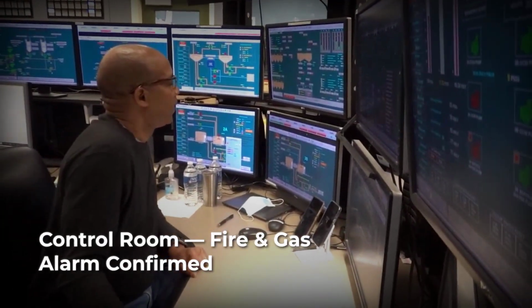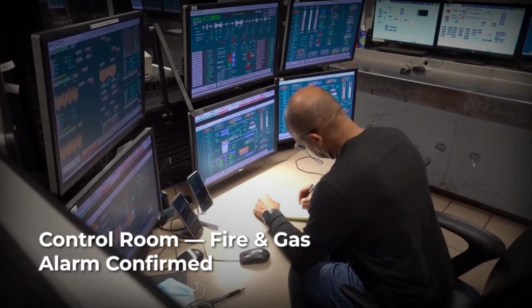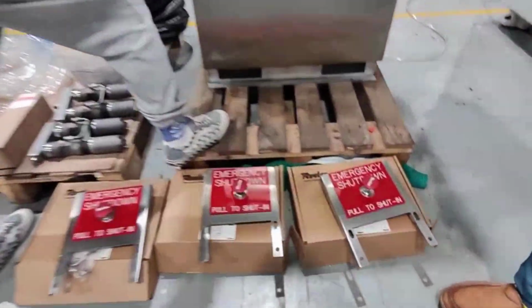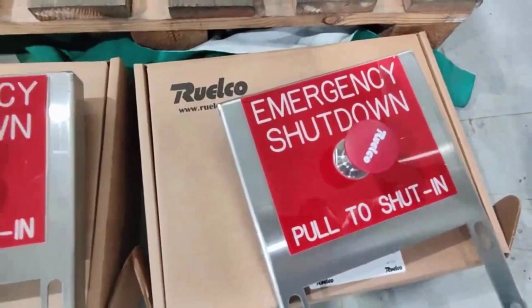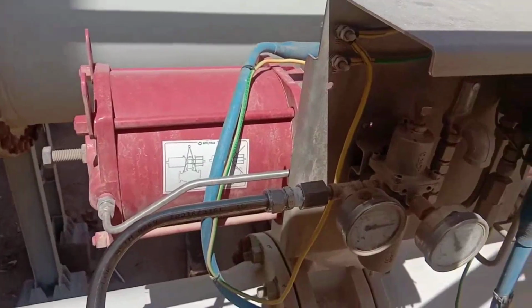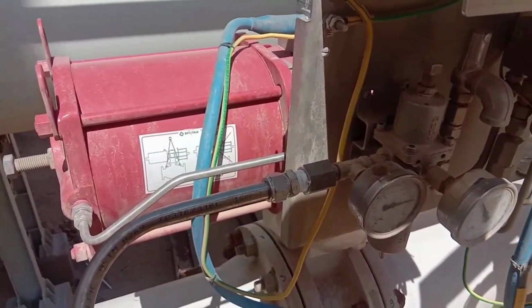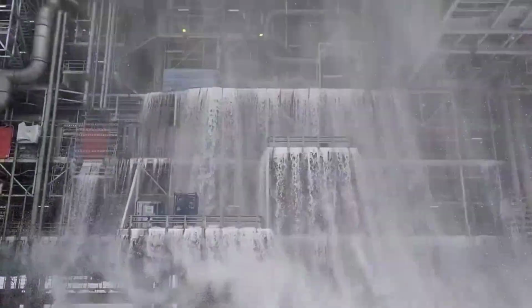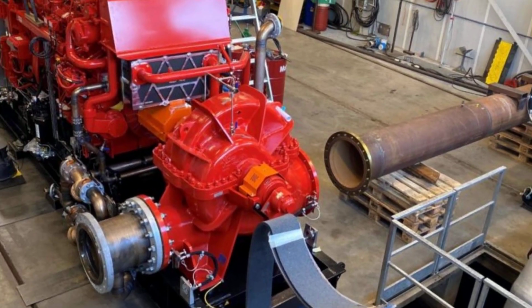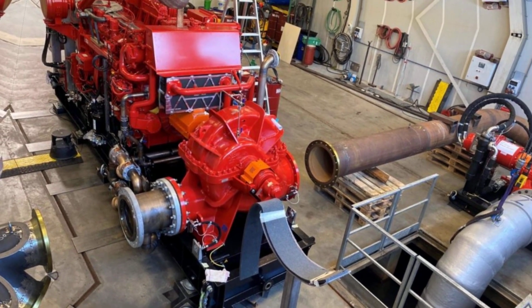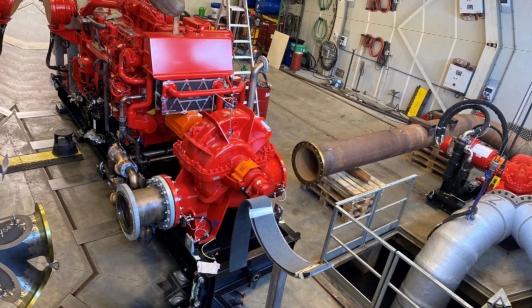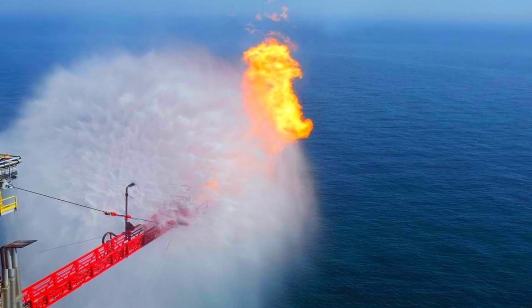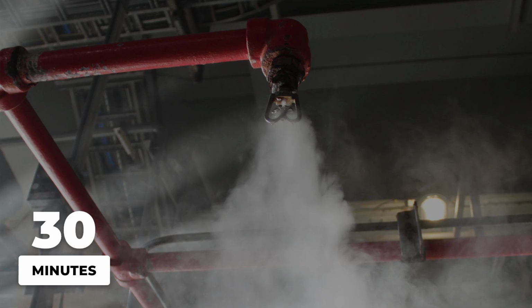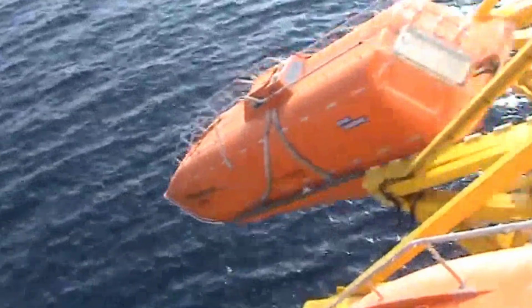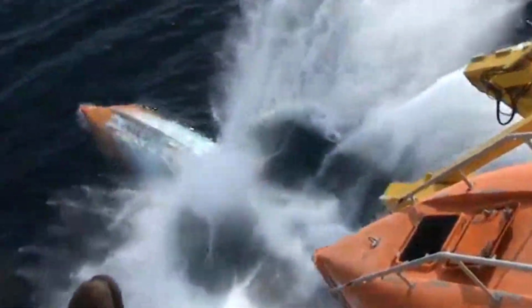Once a hazardous reading is confirmed, the safety officer in the control room initiates the emergency shutdown, known as ESD. Within seconds, automated valves isolate the affected process module, and the deluge system comes online. Dual main water lines, powered by independent pumps and cross-connected to prevent backflow, release a curtain of water across the danger zone. Each deluge system is sized to provide at least 30 minutes of continuous coverage, buying time for suppression and evacuation if needed.